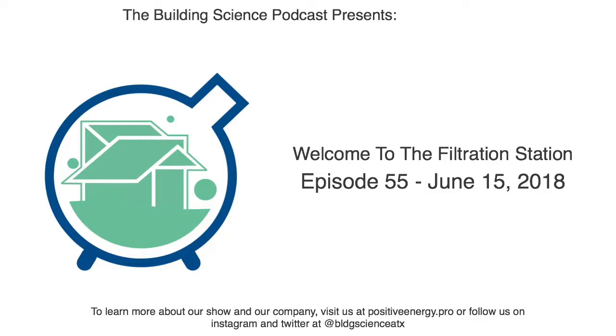The ultra fines. Yep, the higher your MERV goes. So like a MERV 8 filter doesn't have to have any efficiency in an E1 channel, your microfine, but it has to be greater than 70% efficient in the E3. And E3 is 3 to 10 micron range. Where you go to a MERV 13, it has to be greater than 50% in the E1 channel.